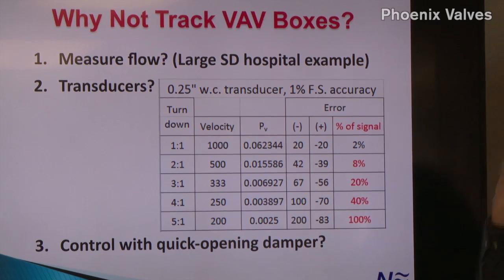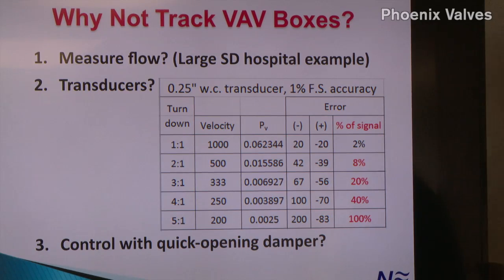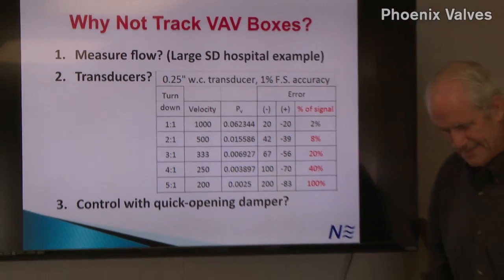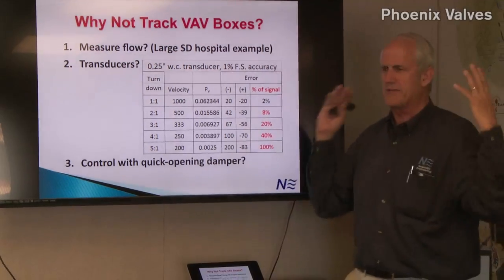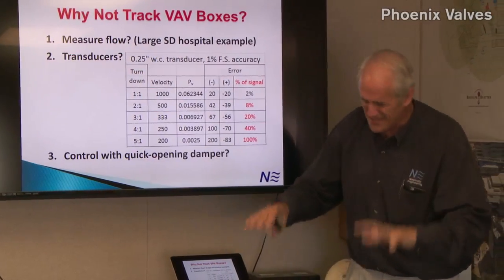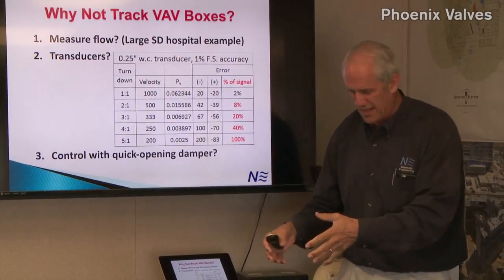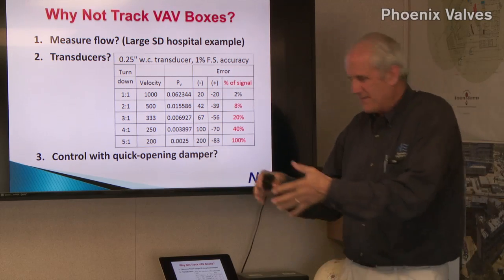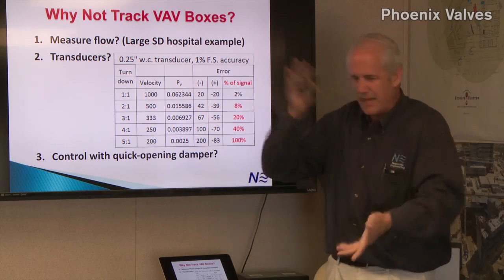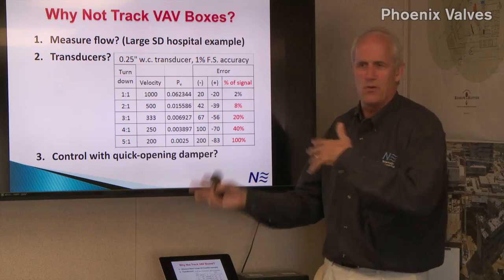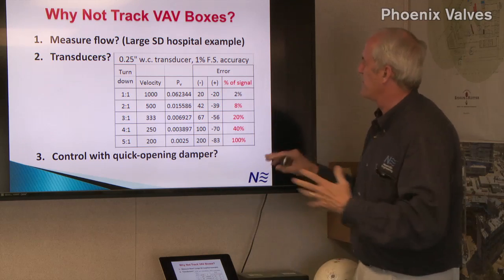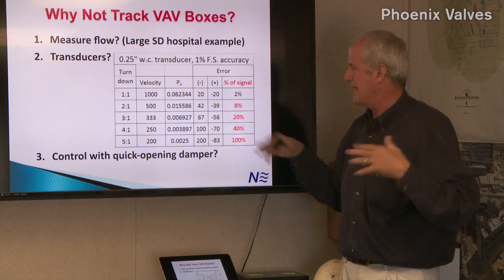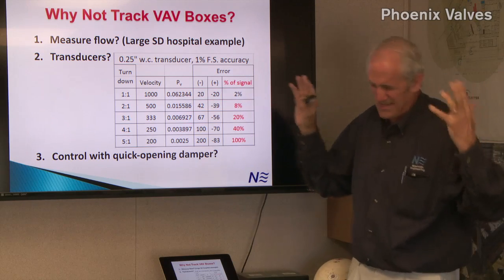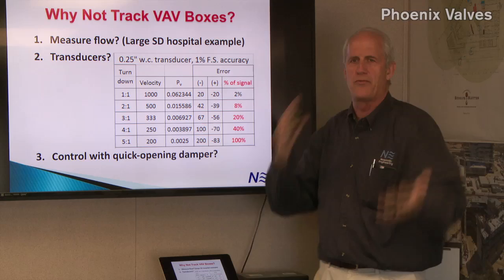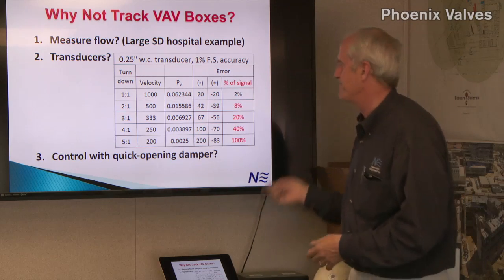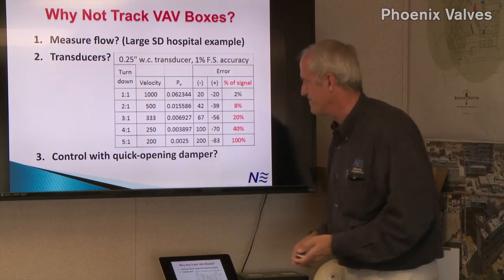And we had a flow measuring station, but it was in a bad location. When we were flowing 40,000, a big built up system, sometimes the station would measure 40, sometimes it would measure 20, and sometimes it would measure 70. I mean, depending on whether you came up at it or down at it or whatever. So some people say, well, I'll just put a K factor on my box. Well, there's not always a K factor you can use. Sometimes the air flows both directions, and then you really run into problems. So you don't have to worry about that with Phoenix.